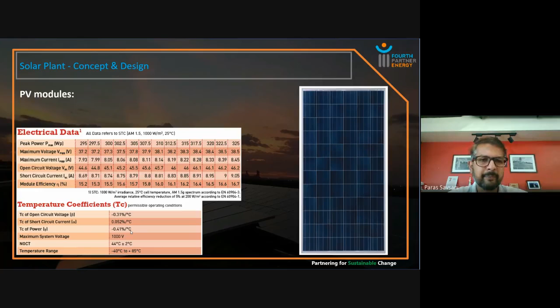Mostly right now 1000 volt DC can be handled by the inverters. So you can combine the total VMP up to 1000, and you have to consider that VMP with some safety margin, so mostly we combine up to 800 or 850. So mostly 20 modules can be connected together. If you see here, the maximum voltage is 37, and if you multiply by 20, it gives you somewhere around 750. That will be the normal range. It can be 20, 21, 22 also, depending on which module you are using.